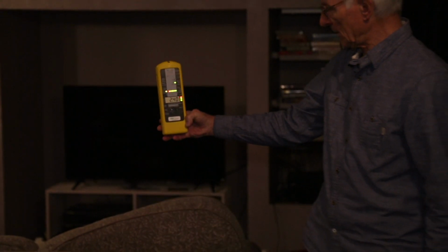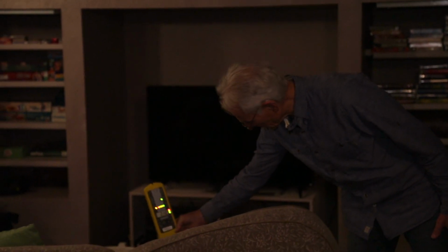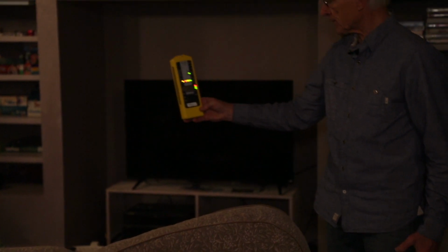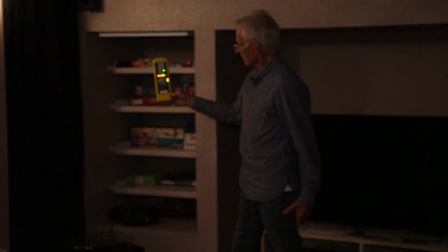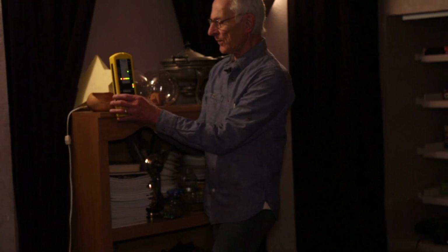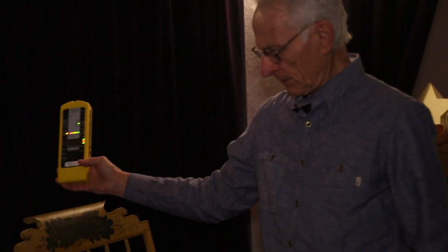As we move into the seating area of the home theater, we're at 2.5 milligauss. 2 milligauss at the seat. It's getting less over toward this side of the home theater, which is obviously moving away from the cables that have that net current on them. We move over this way, and it begins to climb again. And if we choose to sit in this chair here, we're basically at 2 milligauss.